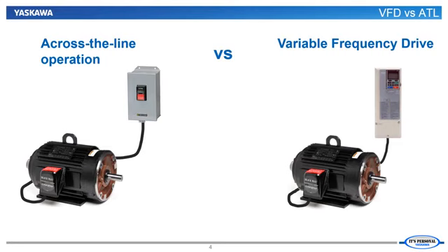Conversely, the VFD can run the motor at whatever speed that the fan or pump system requires. Fans and pumps run by VFDs do not need the dampers or valves. The drive uses only the power needed to match the demand, and the energy saved can provide a return on the investment in less than 3 years.